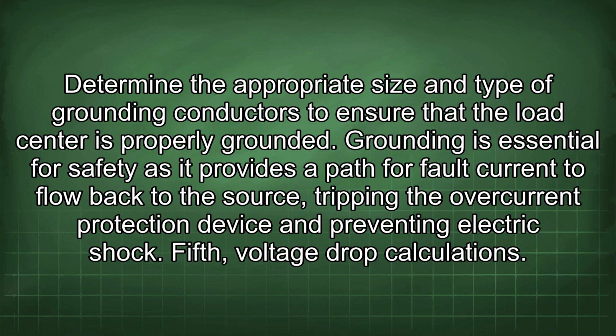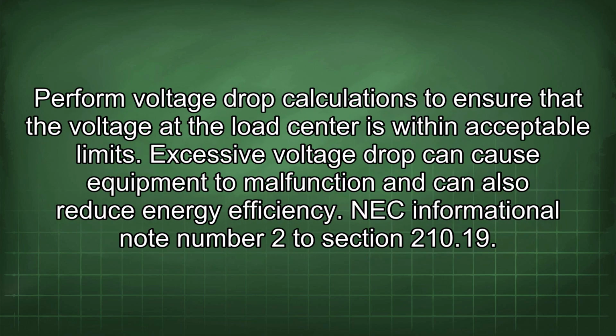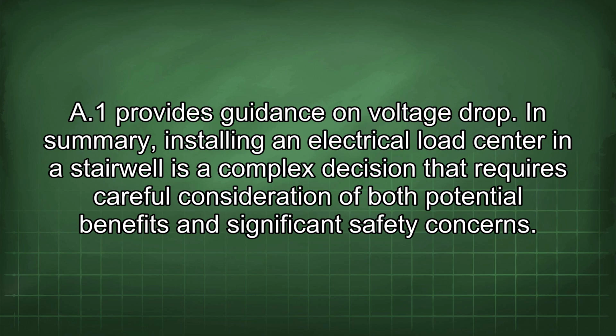Fifth, voltage drop calculations. Perform voltage drop calculations to ensure that the voltage at the load center is within acceptable limits. Excessive voltage drop can cause equipment to malfunction and can also reduce energy efficiency. NEC Informational Note Number 2 to Section 210.19(A)(1) provides guidance on voltage drop.